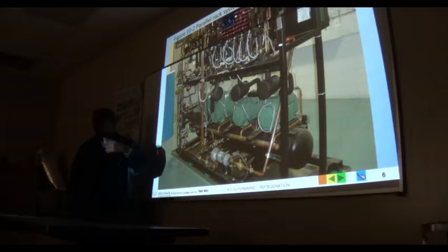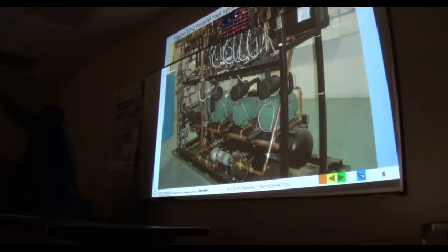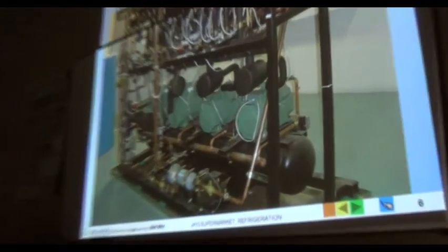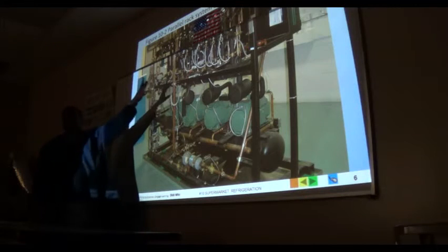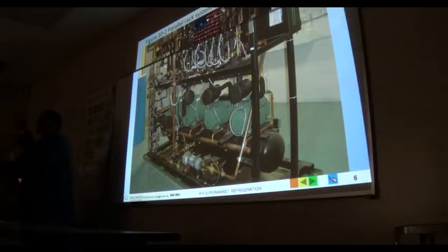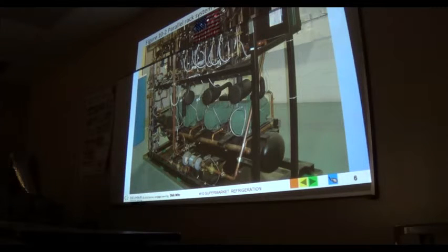With the newfangled thermostats we have now, they can put a sensor in the box and bring the thermostat right into a main controller. So all you may see is a little shiny thing like this, which is, in this case, a PTC thermistor, whose resistance varies with temperature. PTC is positive temperature: as temperature increases, resistance increases. For sensing lower temperatures, they may have the NTC, which is negative temperature. As the heat increases, resistance decreases. That's why it's negative. It works contrary to the other ones.